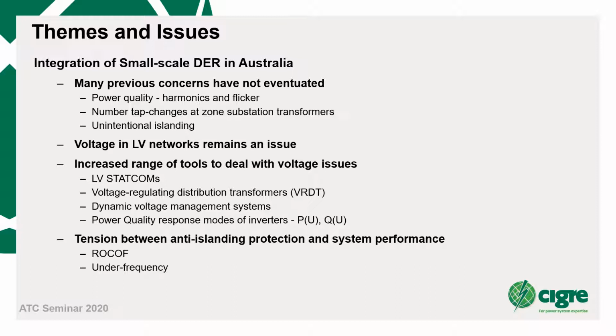However, there are an increasing number of tools available to network owners to mitigate such problems. Whereas in the past, the solution to a voltage problem may have been to upgrade the network, other options available now, or that are being trialled, include low voltage STATCOMs, voltage regulating distribution transformers - that is, distribution transformers fitted with on-load tap changers - and dynamic voltage management systems. PV inverters also include features to help with voltage management, such as the so-called power quality response modes.